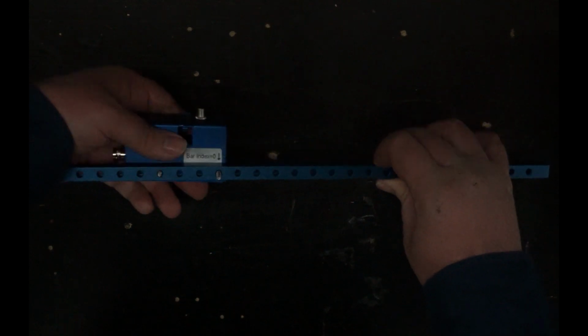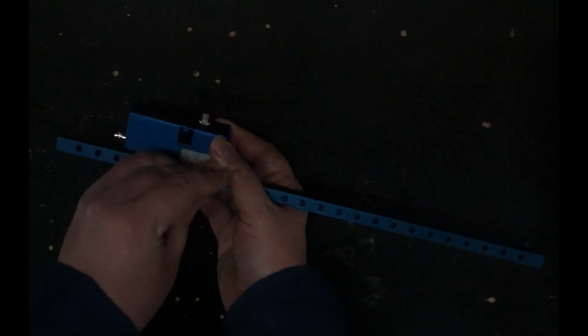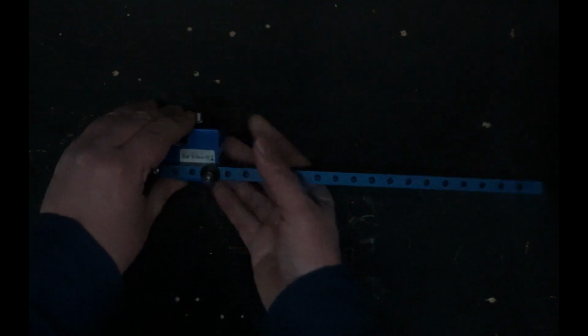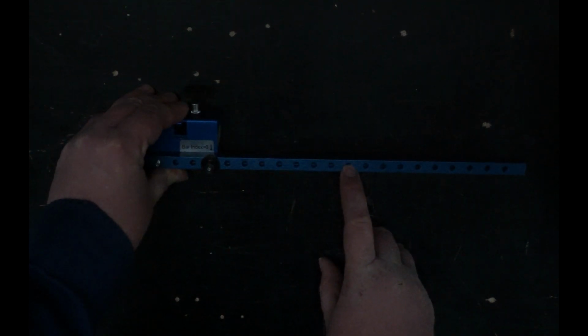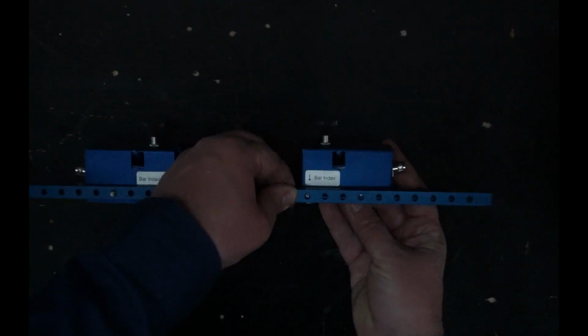To mount the transducers to the mounting rail, start by installing the first transducer slightly off-center, making sure the BNC connector is facing outwards. Now start counting at the next hole towards the center. Install the second transducer into the hole indicated on the mounting window, in our case, in the 8th hole. The BNC connector of the second transducer also facing away from the first. Now that the transducers are installed to the mounting rail, you are ready to install the assembly to your pipe.